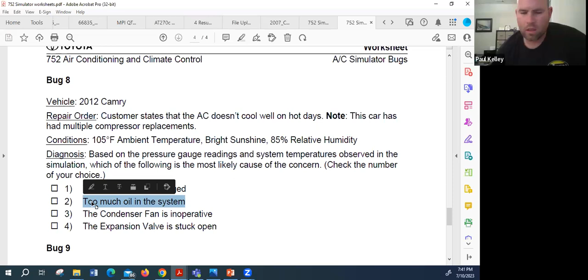So see why I'll take you back to the first week when we learned the physics of AC. We desperately need that condensation in the condenser, and we desperately need that evaporation in the evaporator, or we're not going to get cooling even if our pressures look fine. You know, if you basically pressurized it with water, you could get 300 on the high and 30 on the low, but it's not gonna change states at the right pressures, so you would lose the advantage of the latent heat changing state, moving heat like that. So oil in the system would cause this.